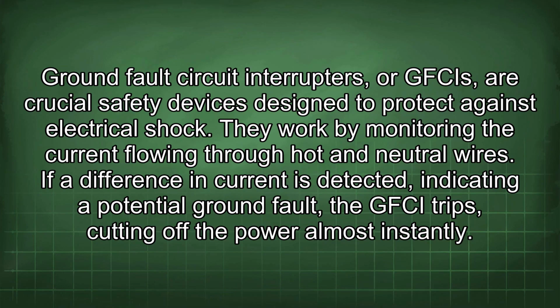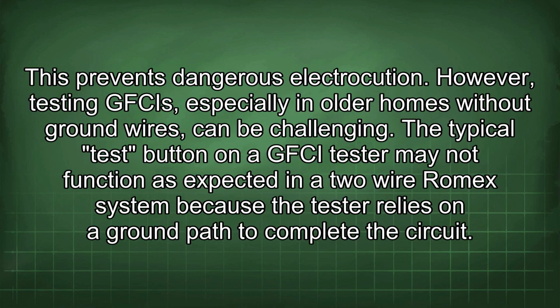Ground fault circuit interrupters, or GFCIs, are crucial safety devices designed to protect against electrical shock. They work by monitoring the current flowing through hot and neutral wires. If a difference in current is detected, indicating a potential ground fault, the GFCI trips, cutting off the power almost instantly. This prevents dangerous electrocution.